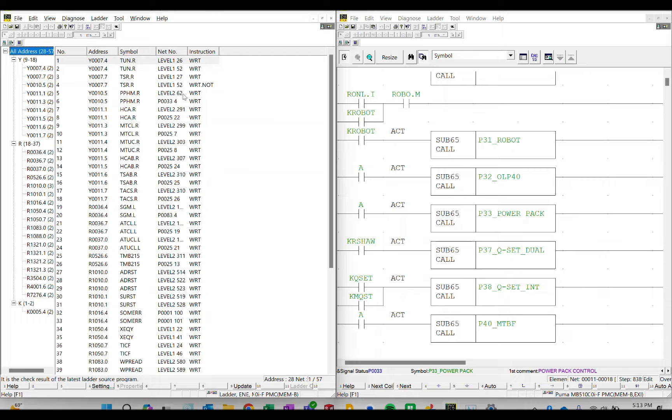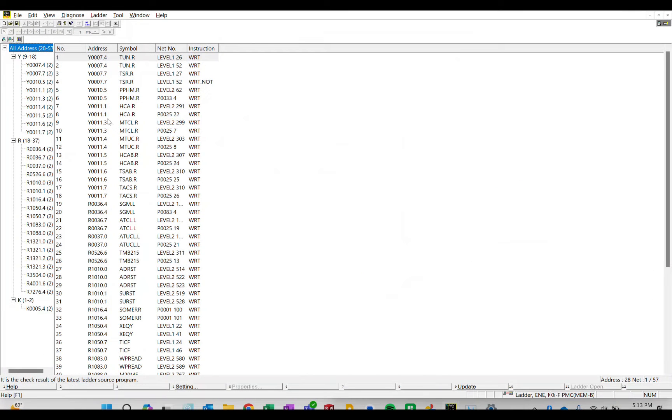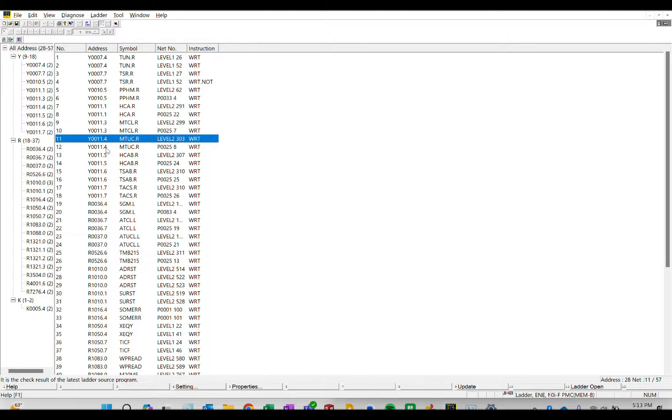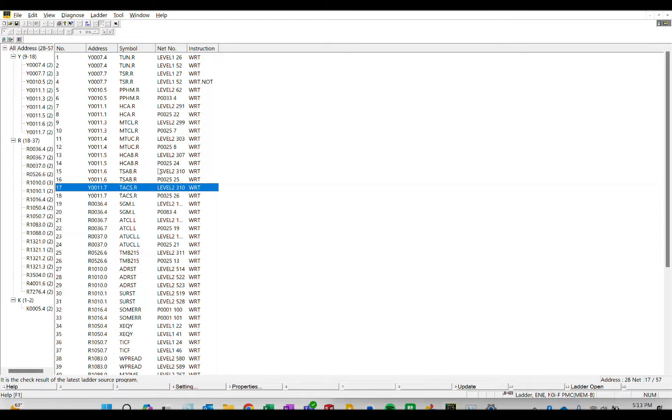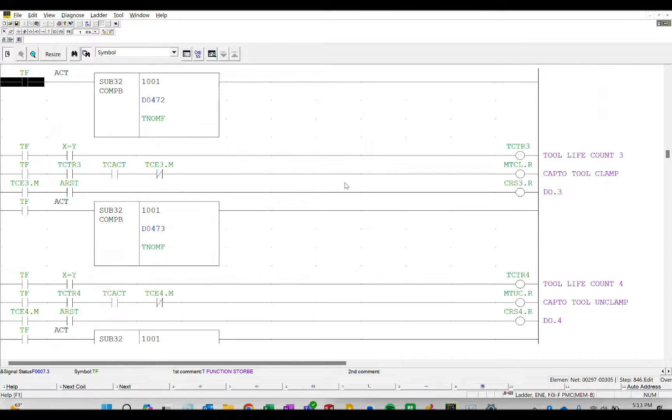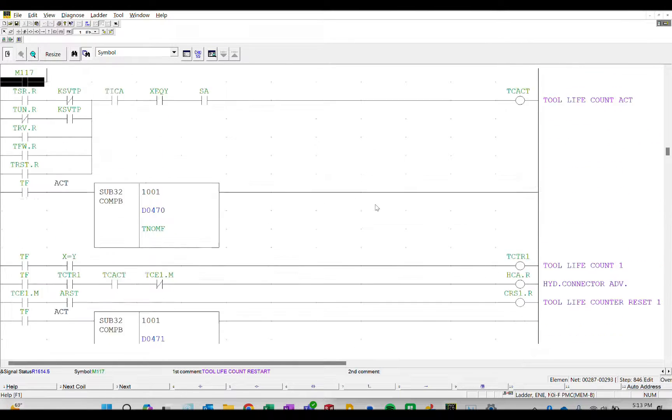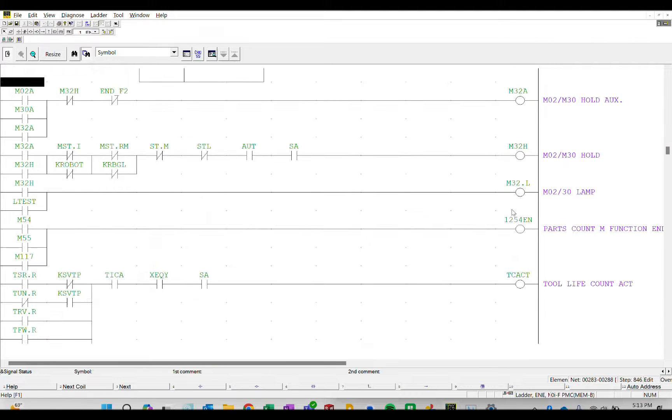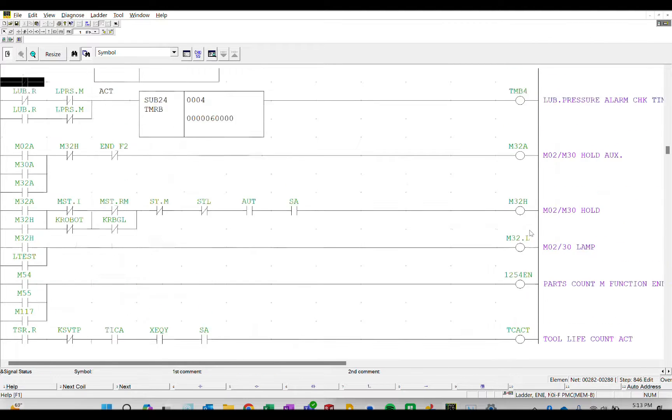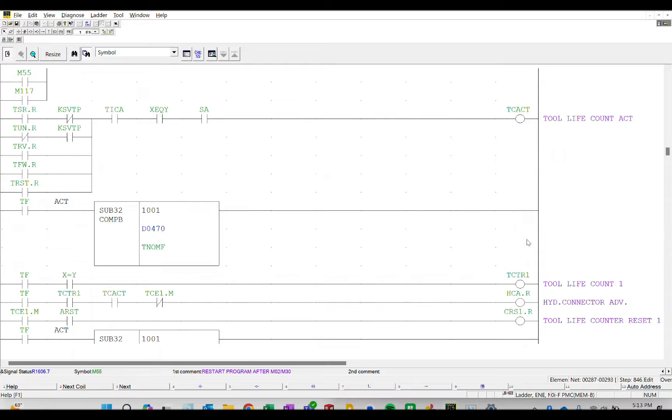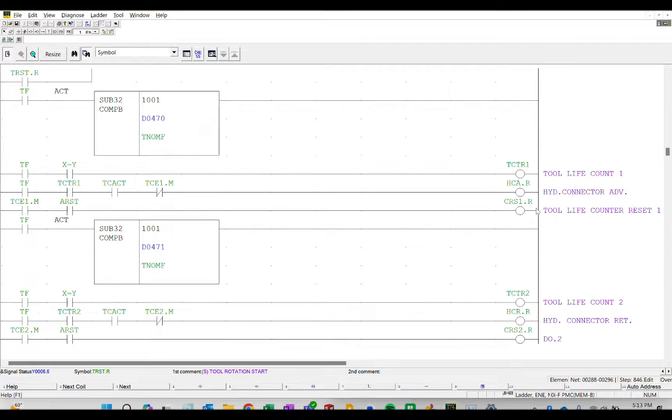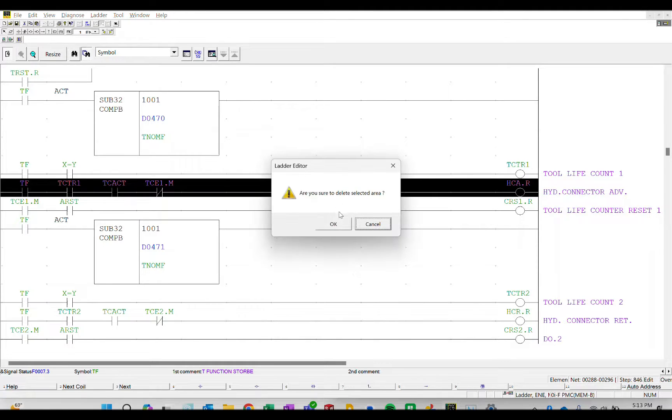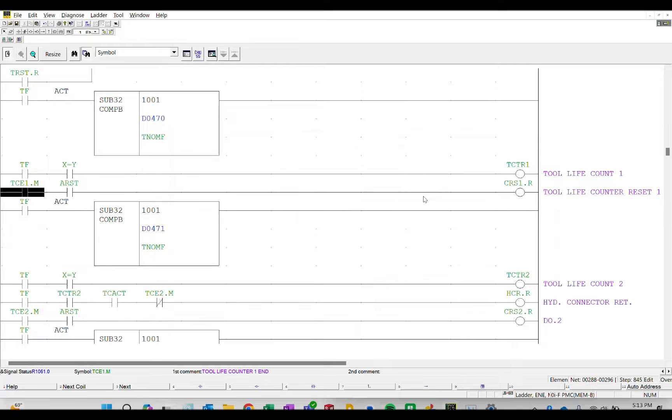I'm going to make this bigger. So we've got Y11.1, not two but three, four, five, six and seven all have problems and they're all in about rung 300. What it is, it's this tool life counter. These are all the bits that we commandeered in this project. So you're going to look for ones that don't look like tool life counter. So here's number one - highlight it, delete it. Say okay, scroll down some more.